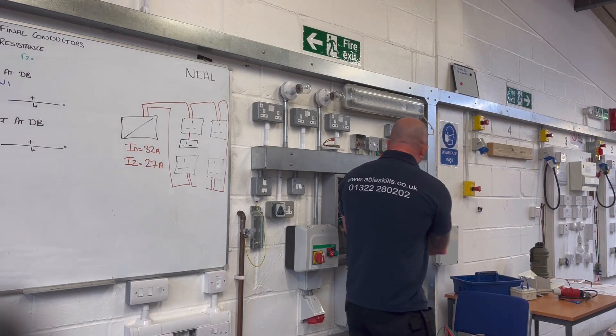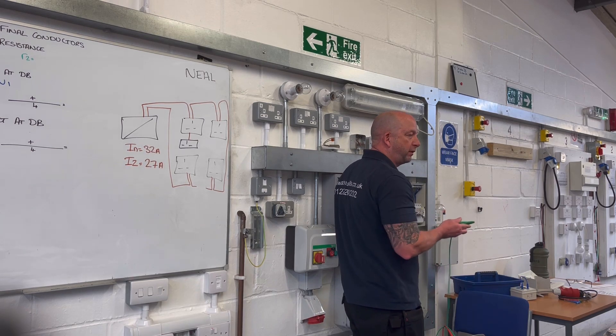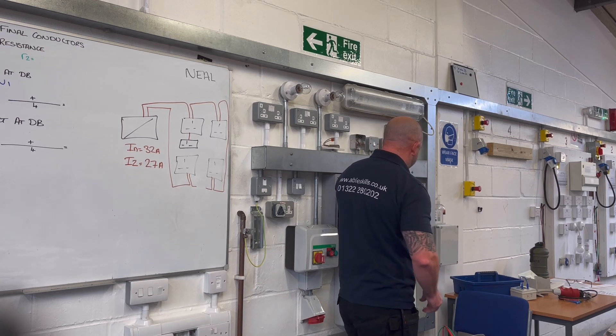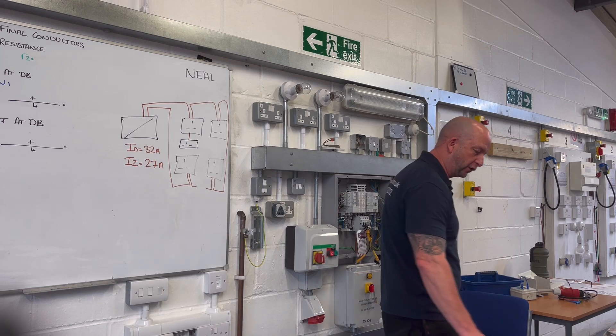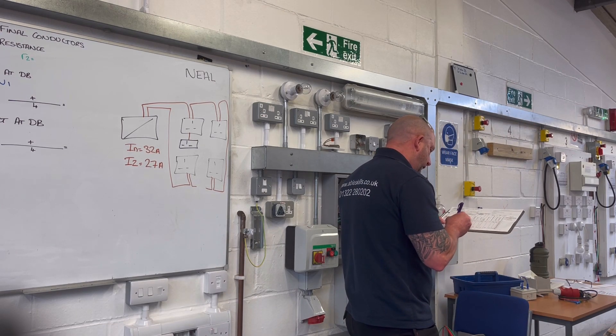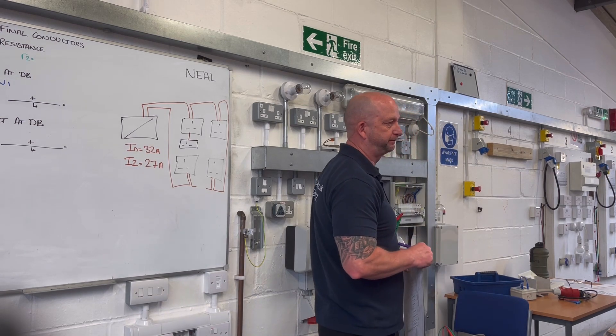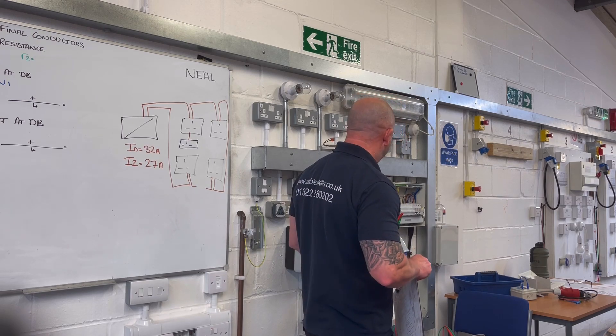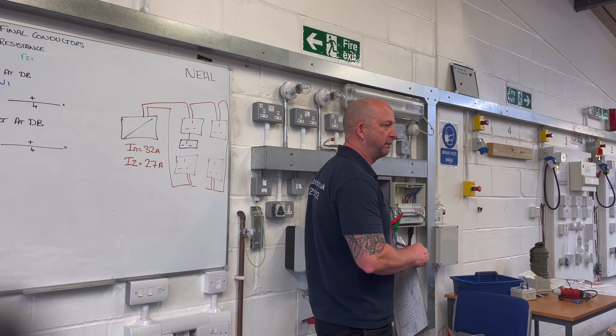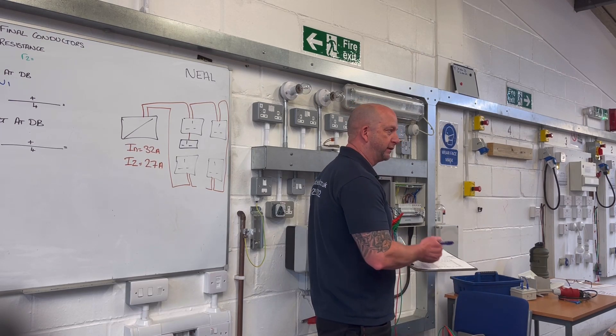I'm going to do the same with the neutral loop. In terms of resistance, what should this value be? It should be the same — it's the same cross-sectional area, the same number of connections, the same length, so it should be pretty much the same. I'm expecting around 0.45 — and it is, exactly the same. Now, if we have any discrepancies between those two results, what would that indicate? Loose connections. For example, if the neutral came in at 0.55, that would indicate possibly some poor connections on the neutrals and we'd have to go back and check all our connections.